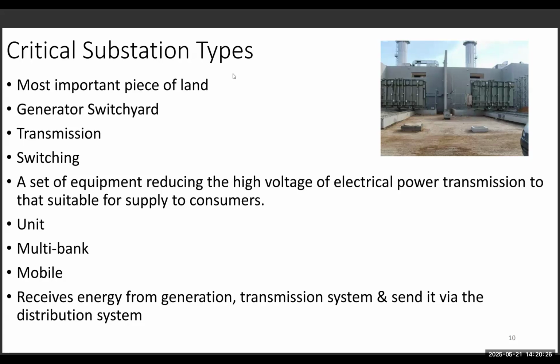So that's why we create the transmission system. The transmission system really starts right at the picture you see in front of you, at the secondary side of the transformer. So it goes in as 11 kV, then it exits, let's say 345. The most common voltage in the country is 345. The highest voltage in the US is 765 kV, but globally we have like 1.2 million volt systems that exist.